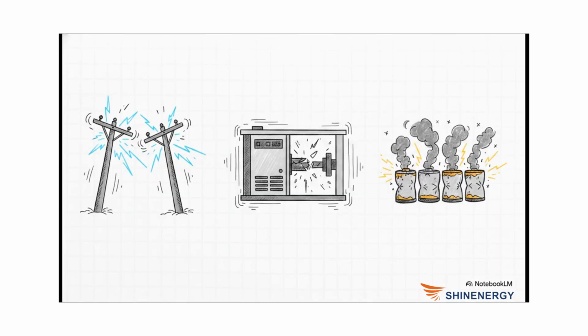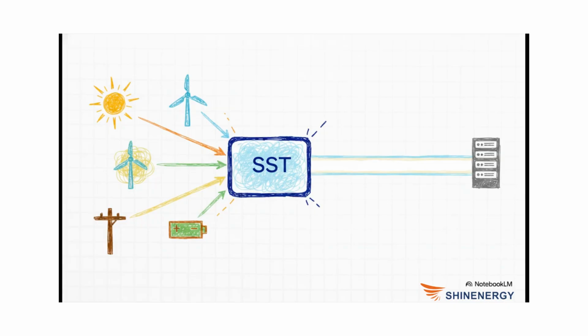Those nanosecond spikes inflict absolute physical violence on legacy grid infrastructure. You simply cannot present this kind of violently pulsating load to standard old-school equipment. It introduces severe harmonics and crazy instability to the utility grid. If you try to power these spikes with backup diesel generators, the rapid oscillation can create a resonance that literally risks tearing the physical steel shafts right off the machines. And if you try using standard batteries, the high-frequency charge and discharge cycles will just completely fry them prematurely. So how do we actually handle this?